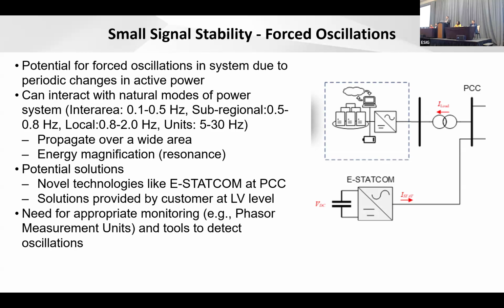So once again, I'll go back to this piece of monitoring. Like power quality I talked about, there's a need for adequate monitoring, same thing here. Even though you do all the analysis, you still need to make sure these data centers don't end up injecting any problematic signals and introduce forced oscillations. So we're looking at things like PMUs that we'd be connecting wherever these data centers are getting connected, and also looking at various tools out there to detect the oscillations and even identify the source of these oscillations.